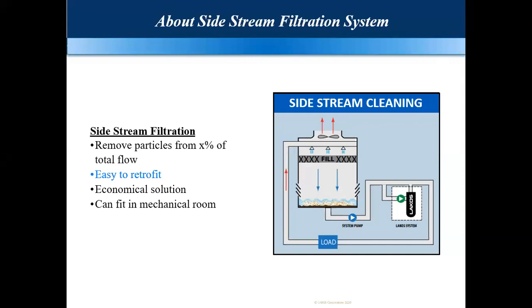You can see when the dirt goes from the condenser pump, the system installation is such that they will have a funnel-type projection in that tapping, right? So it will take maximum dirt to the separator and give the clean water back to the system. So obviously the inflow of dirt to your system will be lesser than your filtration rate, right? So over a period of time, your condenser loop will be cleaner.